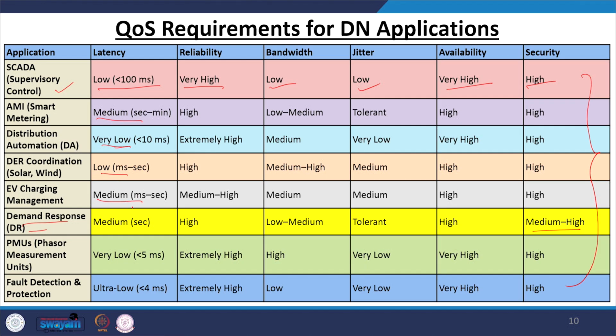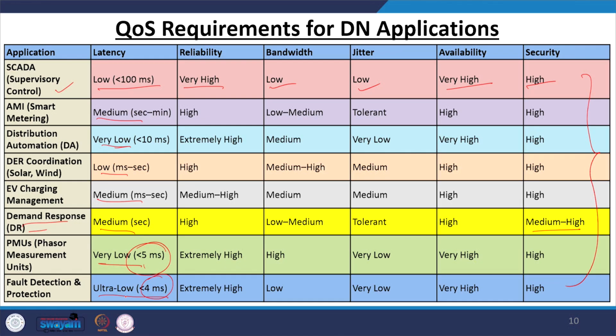EV charging management needs medium latency, demand response needs medium latency, PMU needs very low latency, because that is the data you are using for protection purposes as well. Okay. That means it should reach within 5 milliseconds, you can see, and for fault detection it is ultra low. For your protection devices, you have to clear the fault within 2 milliseconds. If your data is not reaching at the proper time, even 4 milliseconds is very high; your data has to reach within 1 or 2 milliseconds.